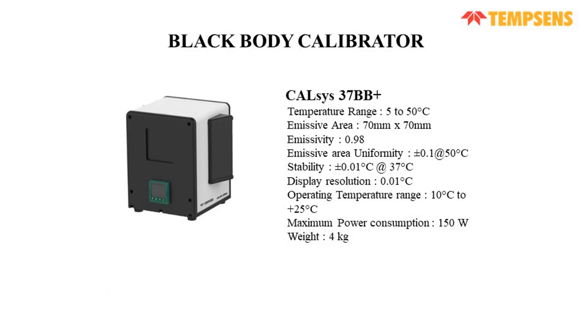Next we have the CALsys 37BB+, and it has a temperature range of 5 to 50 degrees centigrade. The emitter of this model is 70 mm by 70 mm. It has emissivity of 0.98, and the emissive area uniformity is plus minus 0.1 at 50 degrees centigrade. Stability is plus minus 0.01 at 37 degrees centigrade, the display resolution is 0.01, and the operating temperature is 10 to 25 degrees centigrade. The maximum power consumption for this model is 150 watts, and it weighs just 4 kg. It is a very lightweight model.